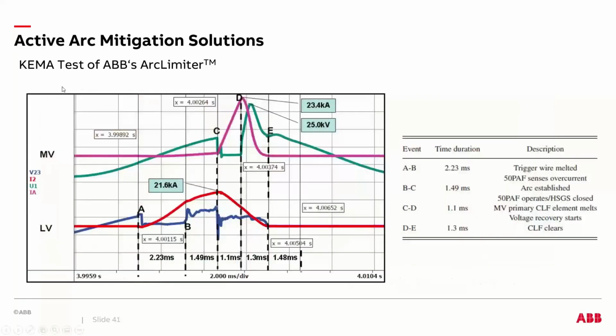And these are the curves that we were able to monitor from the KEMA test, right? So it took about 2.23 milliseconds for the trigger wire to melt and send an arc flash signal to trigger an arc flash element, right? It takes another 1.5 milliseconds for the arc flash relay to operate and send a trip signal to the high-speed grounding switch. And from this point, if you look, the current starts dropping, right?